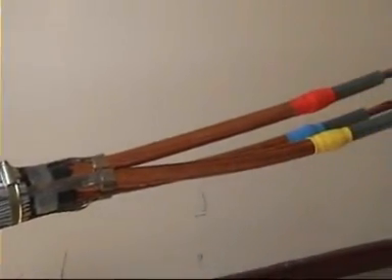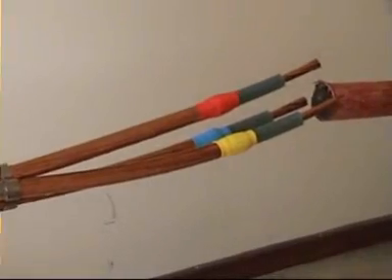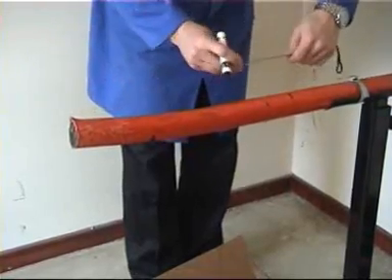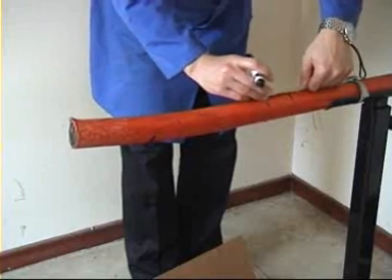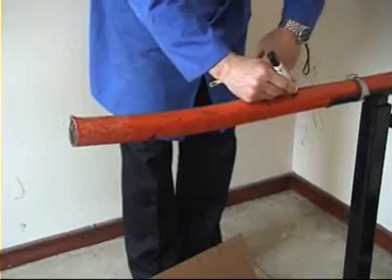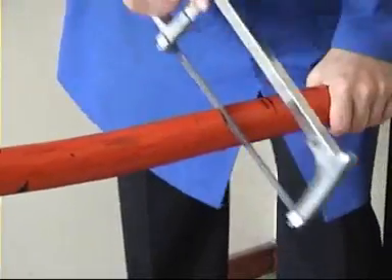The XLP cable is now complete and now we move on to the cable preparation on the PILC side. Again, refer to the instruction sheets measuring out the armours, the lead sheath and the inner bedding.